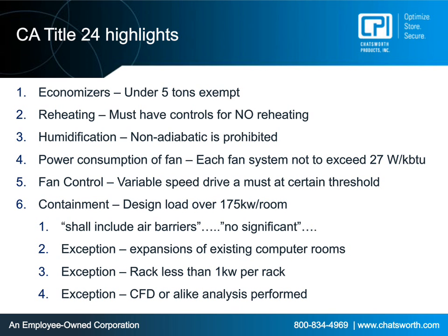So anything above 5 tons, you have to show some sort of economization, some way that you are going to be able to shut down your CRAC units or take outside air or use seasonal cooling to cool your water down. Also, California put in no reheating. On some CRAC units, as crazy as it sounds, there is a reheating element. I will show you in our case study, they actually had a CRAC unit in reheat mode. So California said, no more, you cannot have it on your CRAC unit, no chance to waste energy reheating something that you're trying to cool anyways.